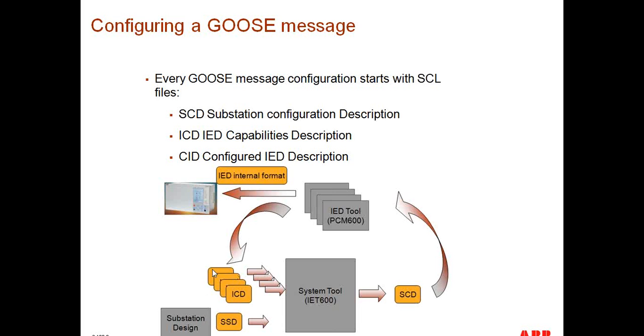And the idea is that you start here in the bottom left-hand corner with all the ICD or CID files from your relays from different manufacturers. You take that information into a system tool. You publish your GOOSE messages. You assign those GOOSE messages as inputs to devices inside your substation. The output of that process is an SCD file, or your substation configuration description, and then that file is taken to the relays, and that file is downloaded to the relays using the individual tool from each manufacturer.